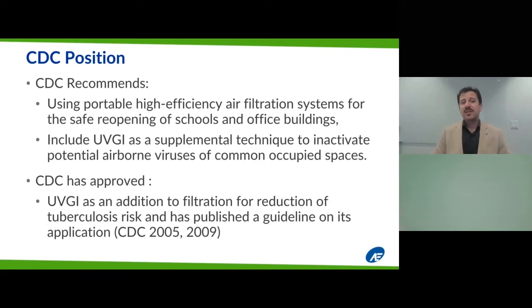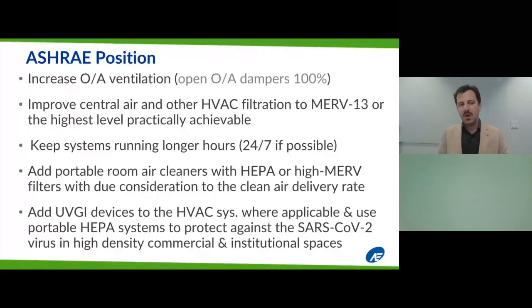As a matter of fact, they have already approved UVGI as an addition to filtration for reduction of tuberculosis risk, and that guideline was published back in 2005. So this is nothing new. We're just trying to use some of those existing technologies to deal with this pandemic. This was about the CDC. However, we have a long list of recommendations provided by ASHRAE, the American Society of Heating, Refrigeration and Air Conditioning Engineers. ASHRAE recommends increasing the outside air ventilation by opening the outside air dampers 100%.